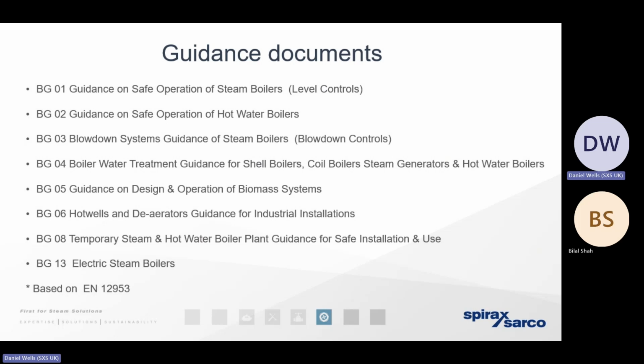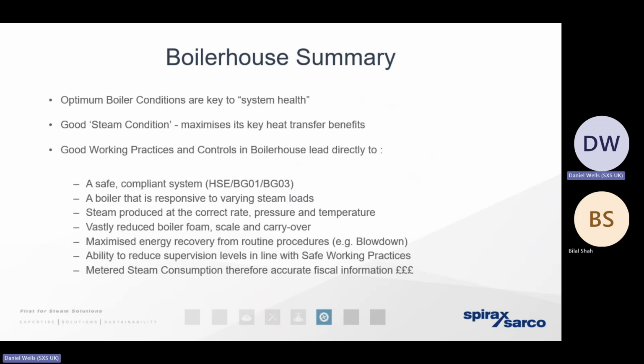They don't care if that steam is contaminating a process or a heat exchanger. They don't care if the boiler's not capable of responding quickly. They don't care if our cost of steam, cost of gas is high. Not their problem. All they care about is that that boiler is operating safely. And that really explains why there are so many different boiler control types. It depends what the client has got an appetite for.